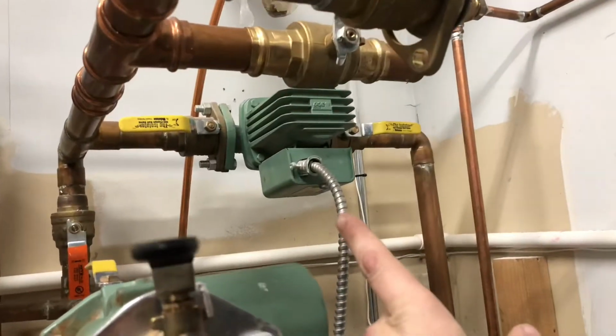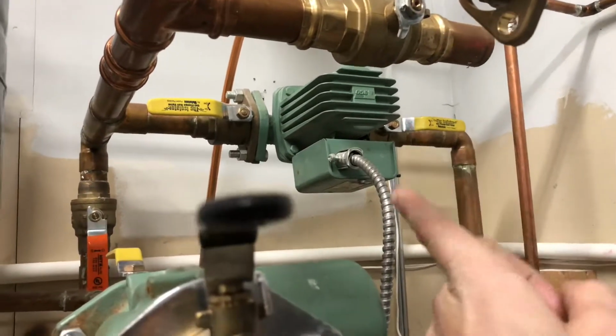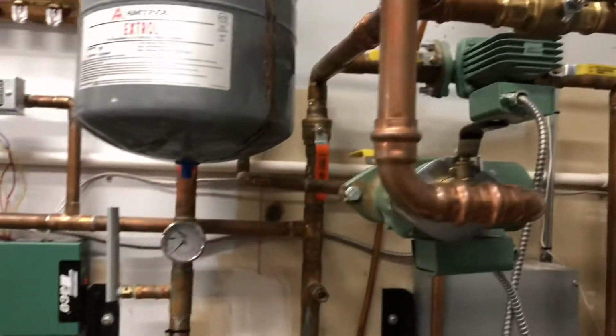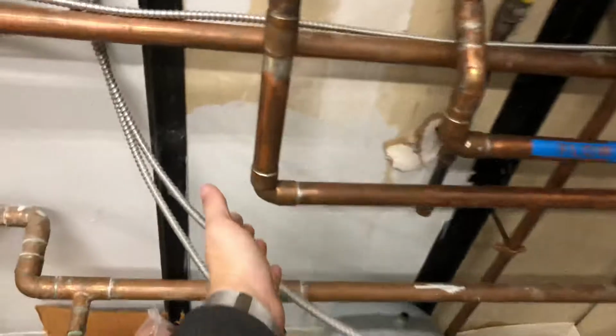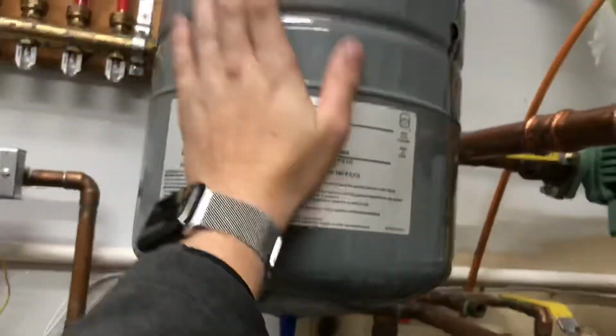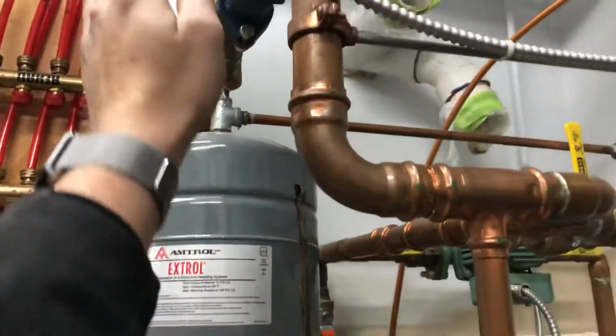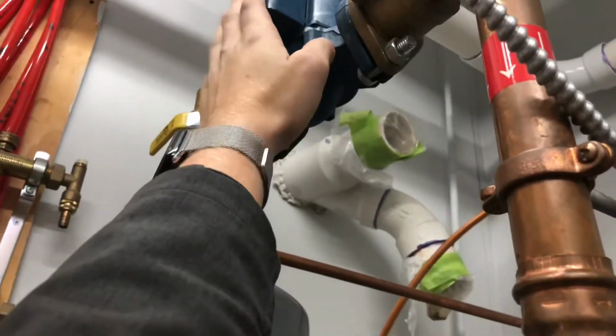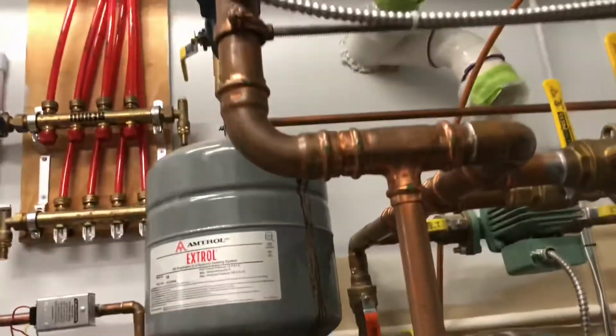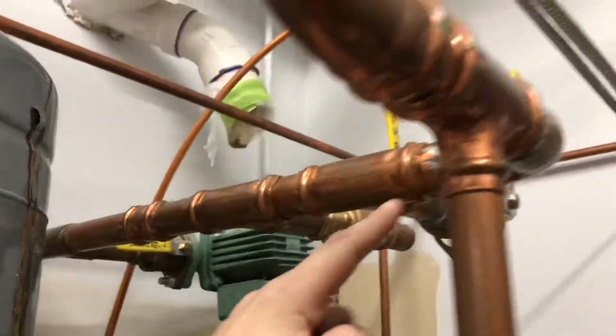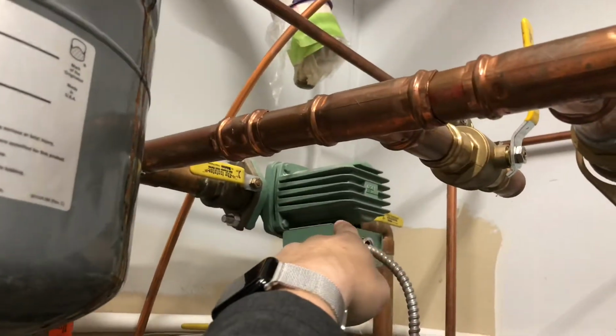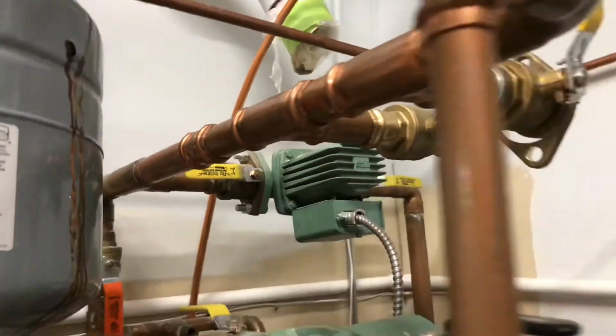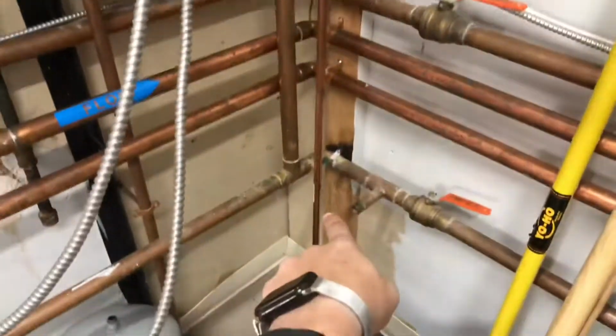So the pump up there is our circ pump for zone 1. So again, this is all on one circuit. Comes in through the hot water here, you got a pressure accumulator here. You don't strictly need a secondary circ pump to flow everything. You can. Comes over here, there's the circ pump for number 1 with a ball valve on either side. Water out from there, and that flows to the zone 1 manifold.